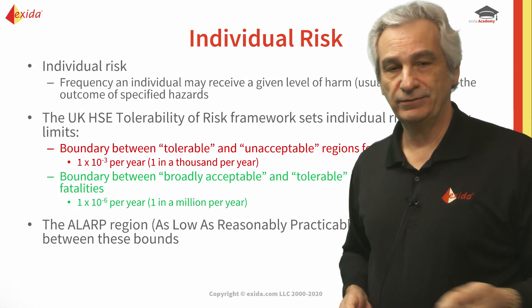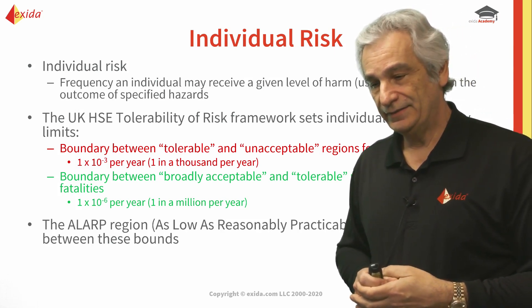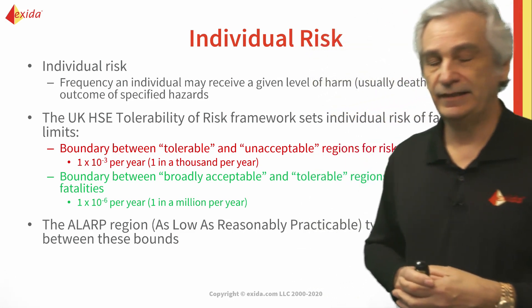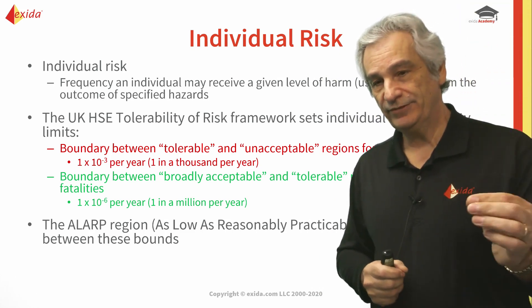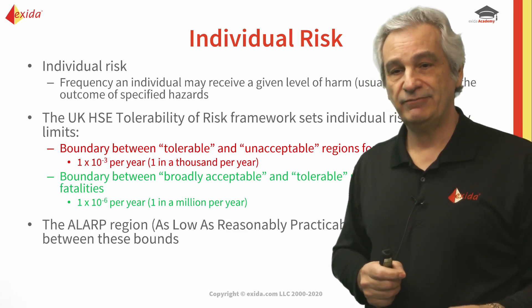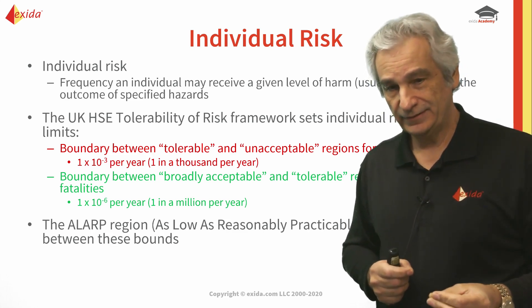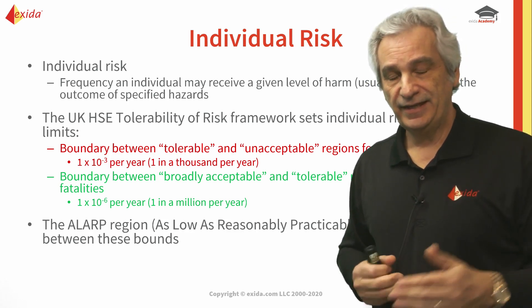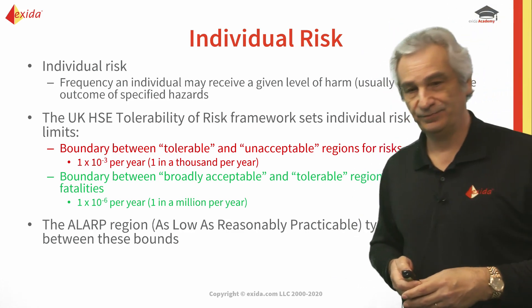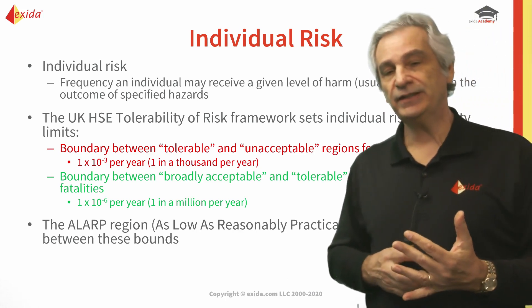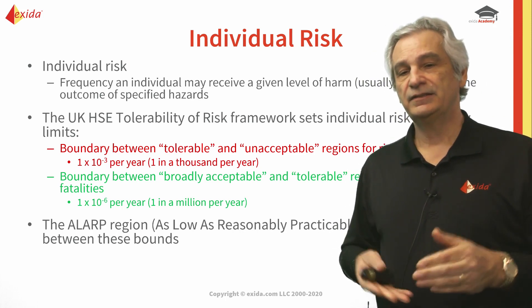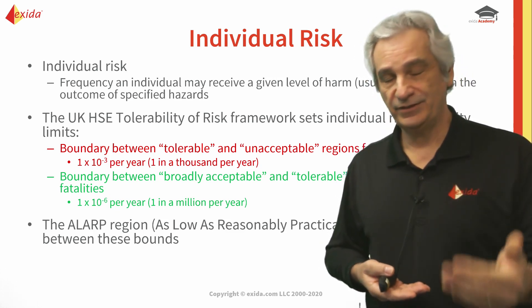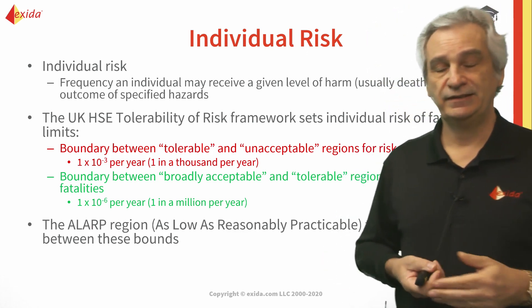The UK Health and Safety Executive defined a boundary for plant operators between one fatality every thousand years down to one fatality every million years. For the public, it's an order of magnitude better: one fatality every ten thousand years down to one fatality every million years. That region is known as the ALARP region. When companies define their risk tolerance they need to consider ALARP. Most companies in the US use either 10⁻⁵ (one fatality every hundred thousand years) or 10⁻⁴ (one fatality every ten thousand years).